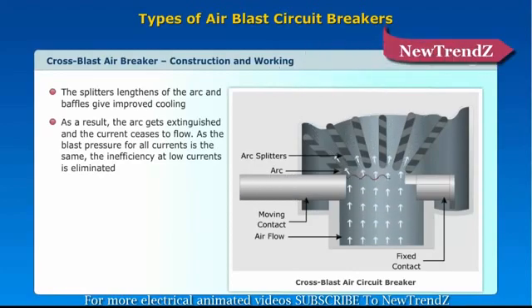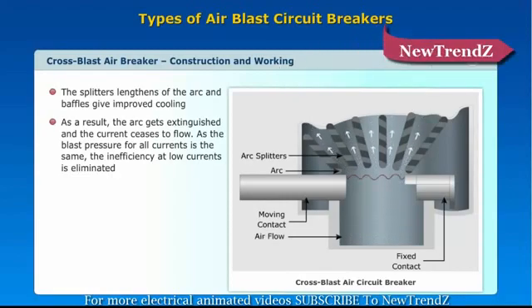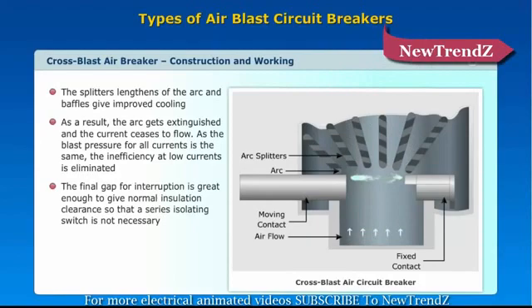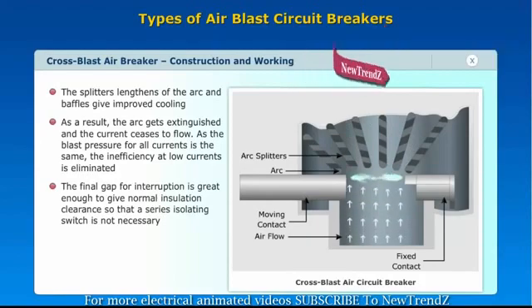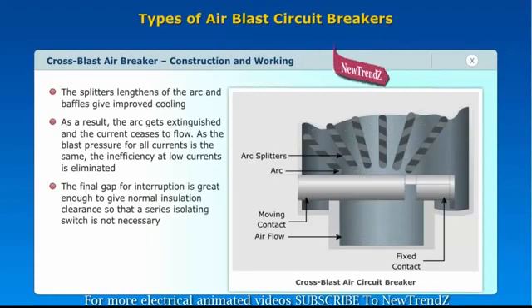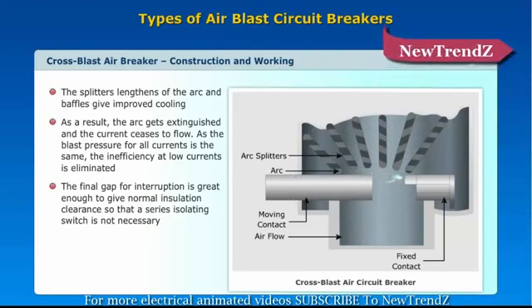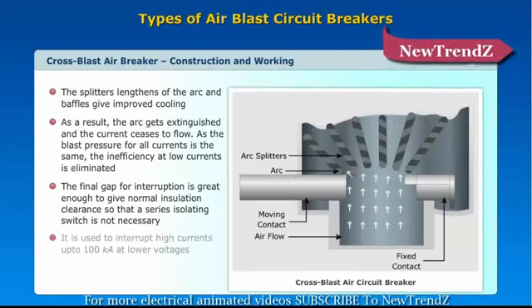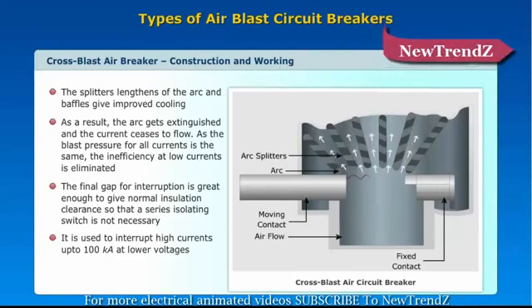As a result, the arc gets extinguished and the current ceases to flow. As the blast pressure for all currents is the same, inefficiency at low currents is eliminated. The final gap for interruption is great enough to give normal insulation clearance, so that a series isolating switch is not necessary. It is used to interrupt high currents up to 100 kA at lower voltages.